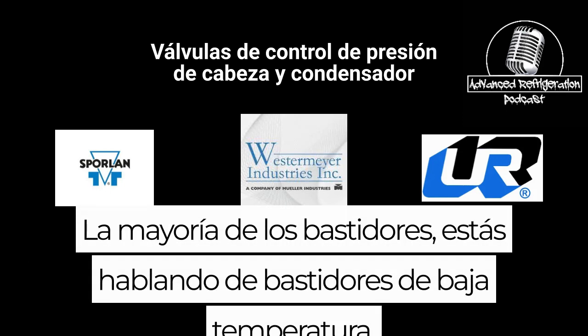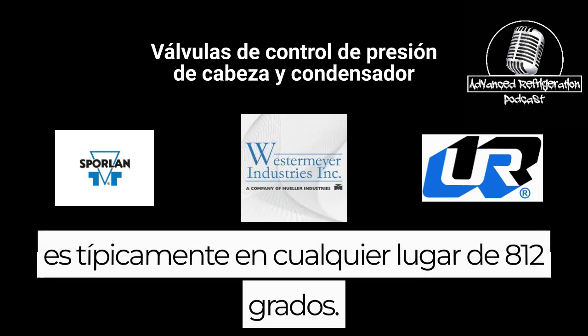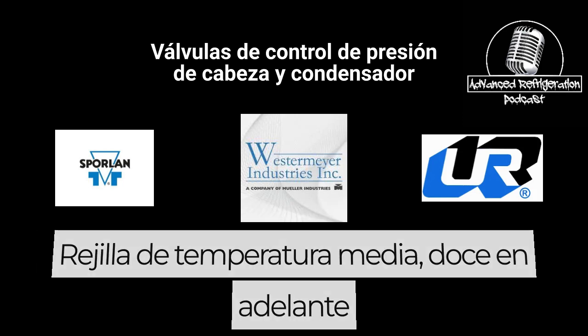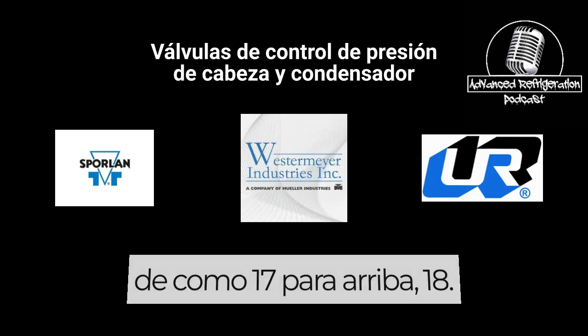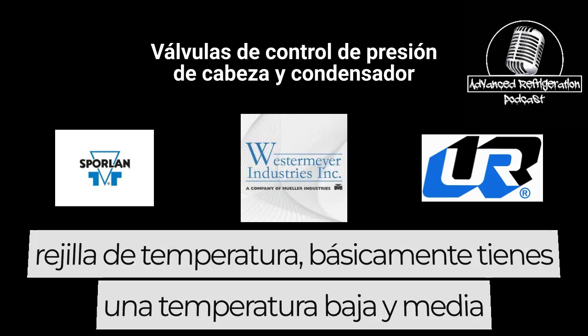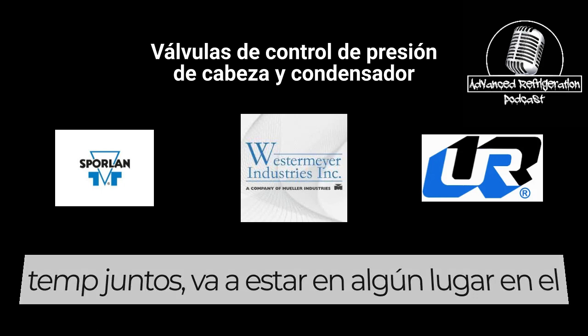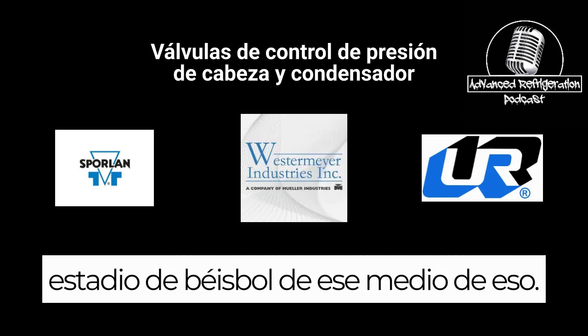Most racks, you're talking about low temp racks, the TD on a low temp rack is typically anywhere from 8 to 12 degrees. Medium temp rack, 12 upwards of like 17, upwards of 18. If you have a split temperature rack, where you have a low and medium temp together, it's going to be somewhere in the ballpark of the middle of that.